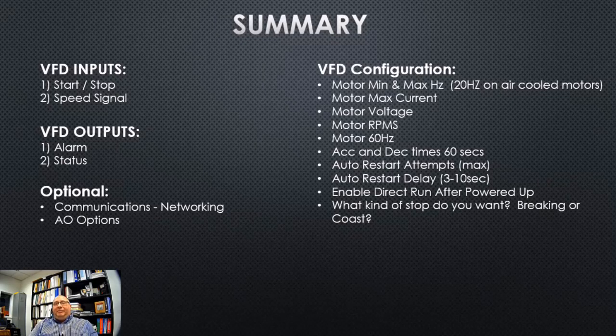Your motor voltage, you're going to need that. Your RPMs, how fast the motor is going to be spinning. What hertz you want to set it for. Typically it's 60 hertz. We have our acceleration and deceleration times. All right, rule of thumb is 60 seconds. We want to auto start the drive. We have to set it up for auto start and maximize the number of attempts that it can auto start. Just don't let it make only one attempt. Auto start delay should be 3 to 10 seconds. And we want to enable direct run after power up.